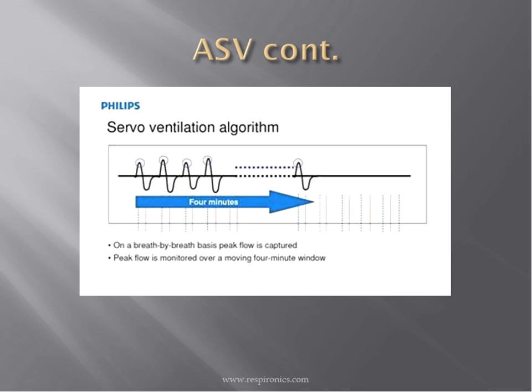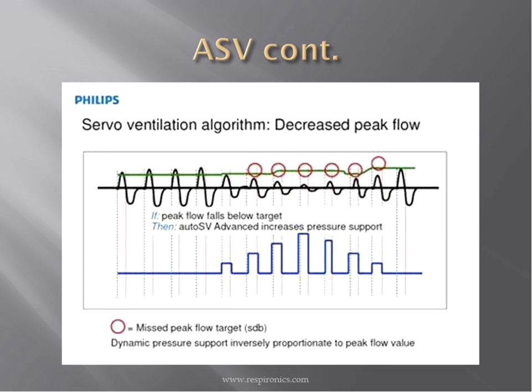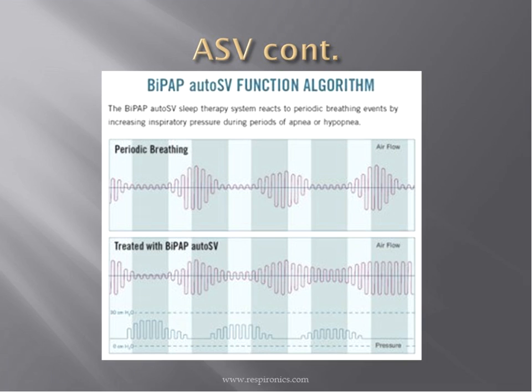So this is the servo ventilation algorithm that Philips uses, and this is, again, just for an example. So what it does is over 4 minutes, it goes on a breath-by-breath basis to capture the peak flow, and it's monitoring it over that 4-minute window to see what the patient's normal peak flow would be. Once it starts sensing the decrease in the peak flow, it starts increasing the pressure support to get it back to the target peak flow that it is falling below.